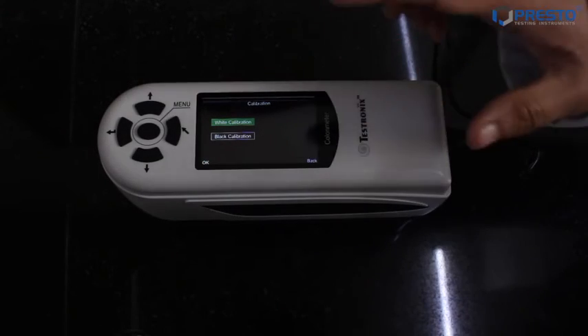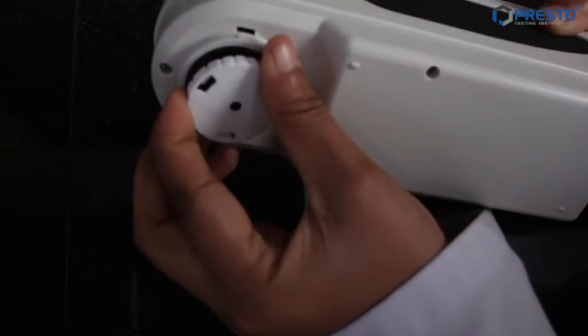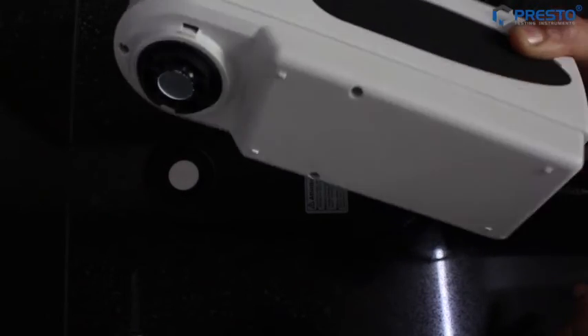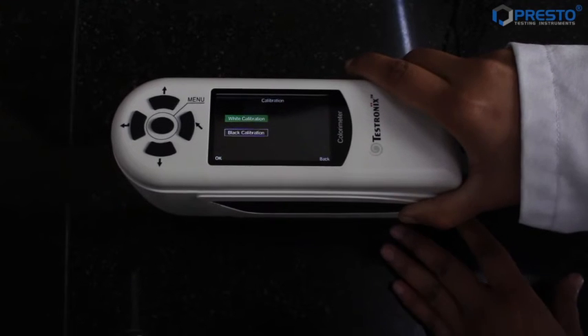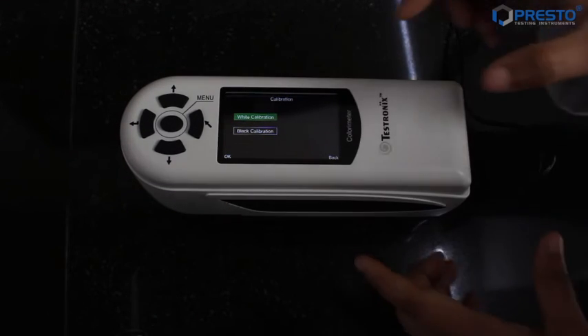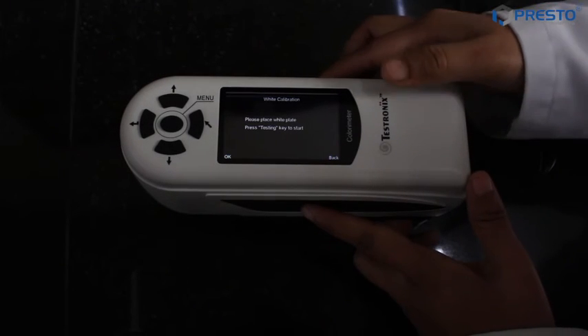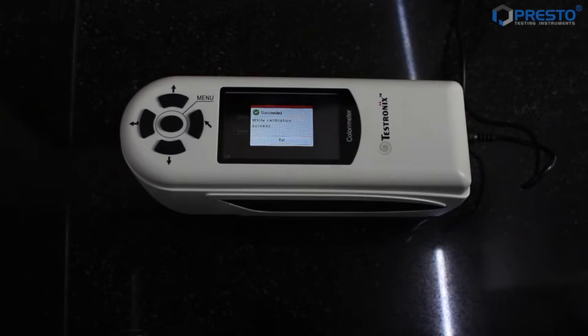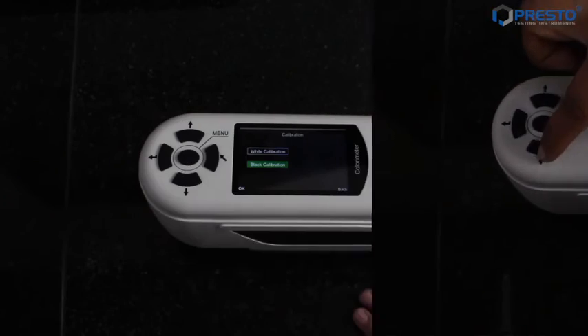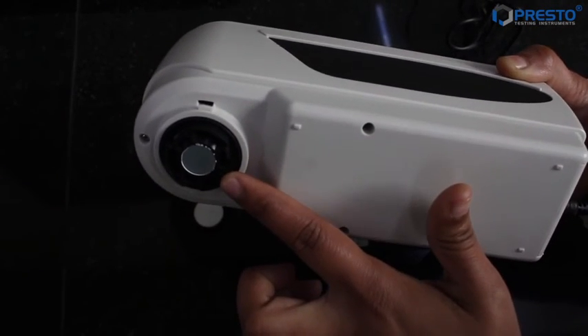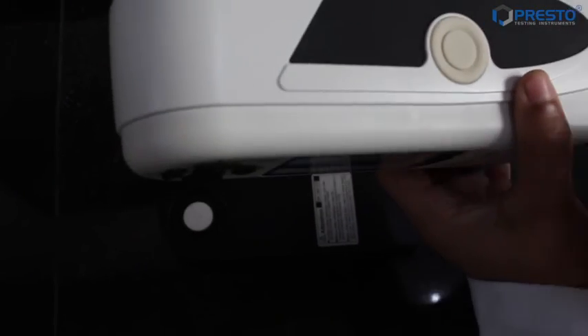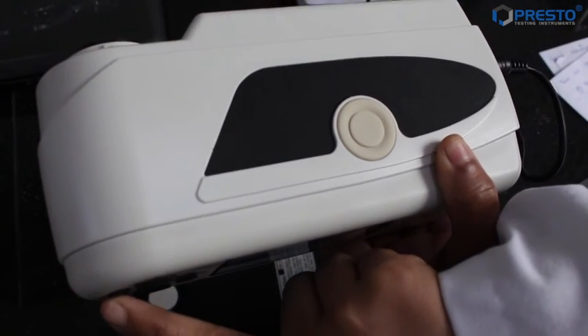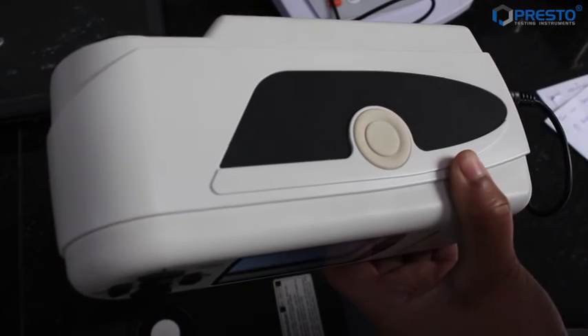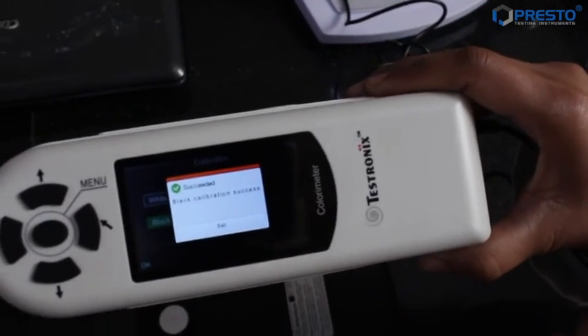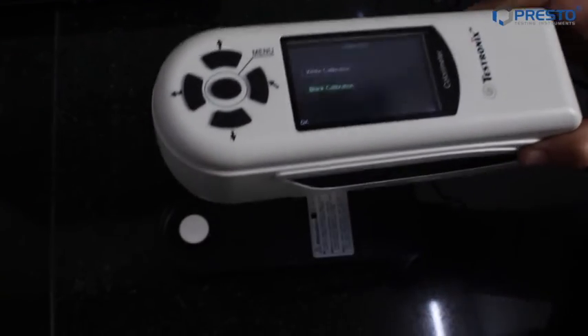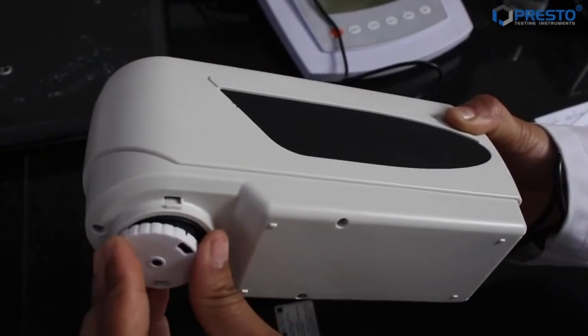So calibration, first white calibration. Open this and then place it over the white plate, then press enter and then press the testing key. It is showing calibration success. Then for black calibration, direct the sensing port to air and then press black, enter, then press the testing key. So it's showing black calibration success. Again fix it for measurement.